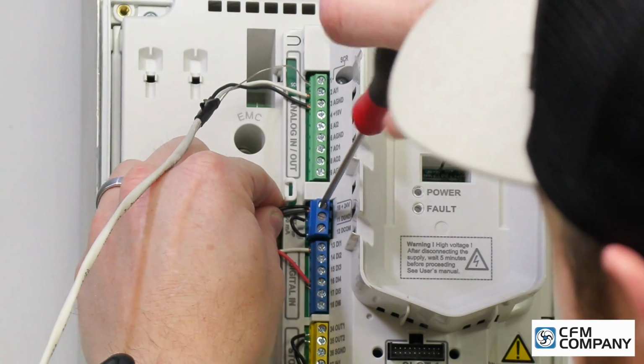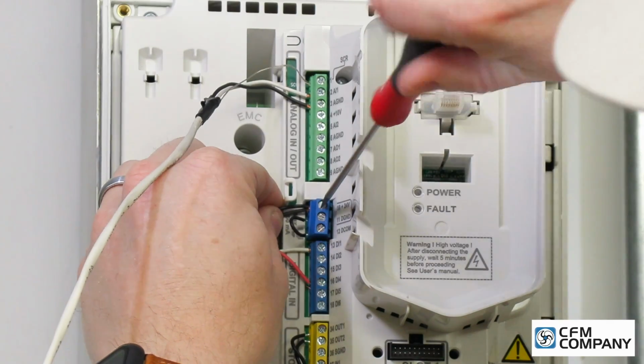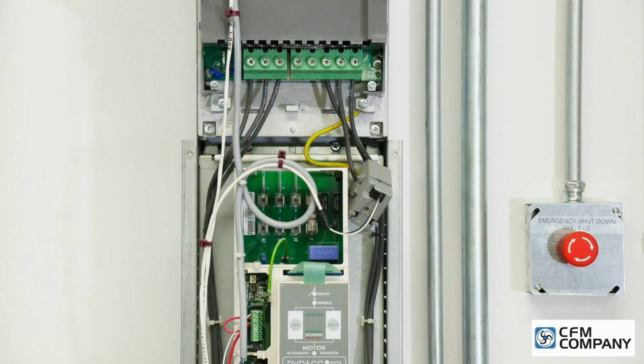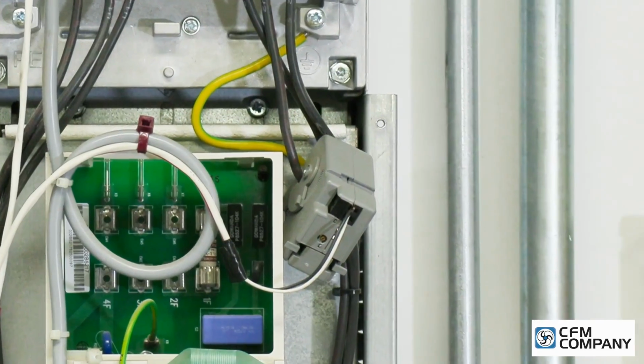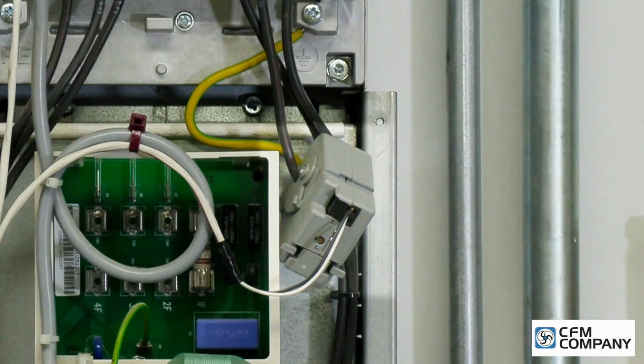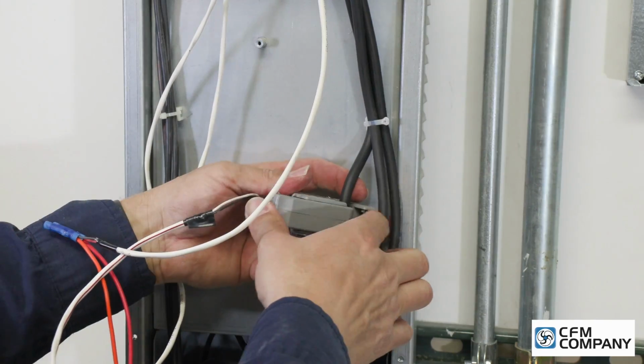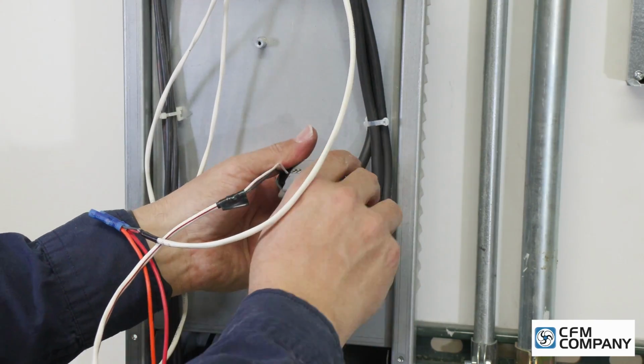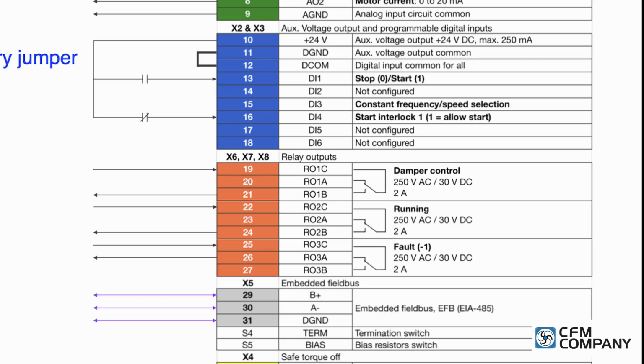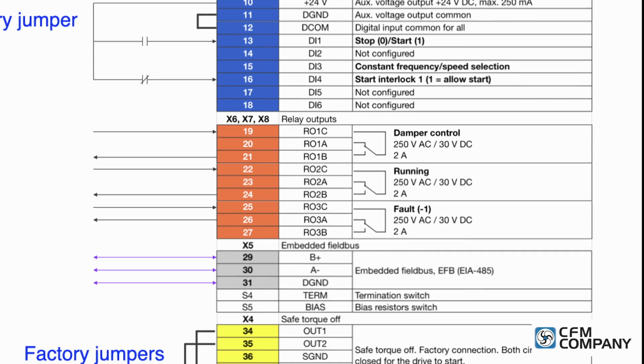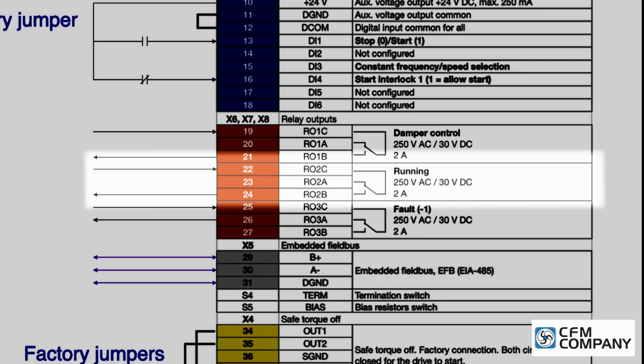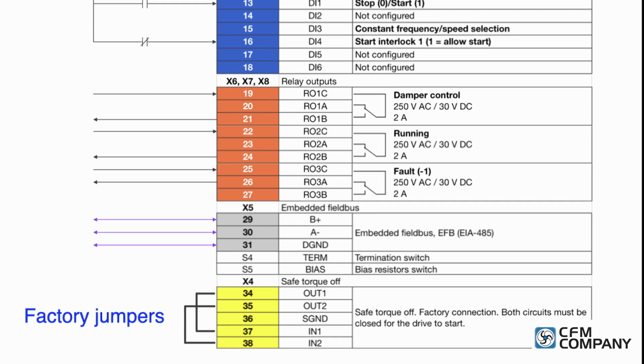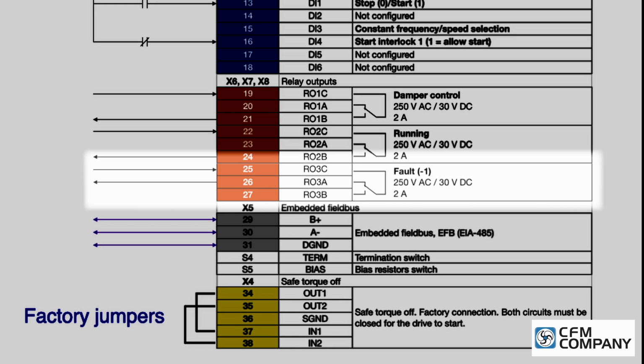Continue to land the field controls to the new ACH580 drive per the appropriate functions. For this bypass replacement, the original field controls used a current switch for status on the motor leg. The original current switch is reapplied to one of the motor legs between the output of the drive and the motor terminal block. If a current switch is not being used, the run status wires will be landed on relay 2, terminals 22 and 24. If a fault status is required, use the fault status relay, terminals 25 and 26, the normally closed contacts. The fault status relay closes on a fault or on the loss of power.